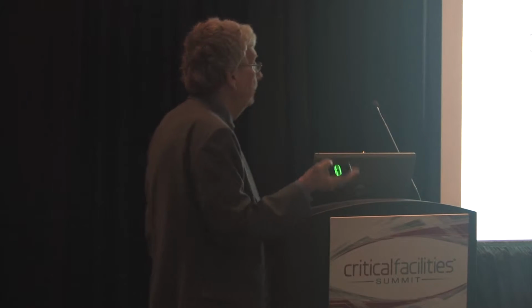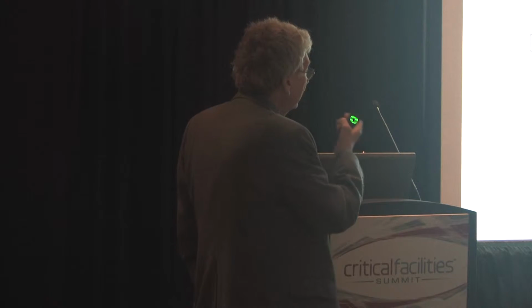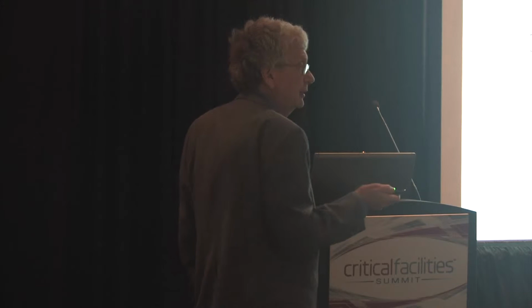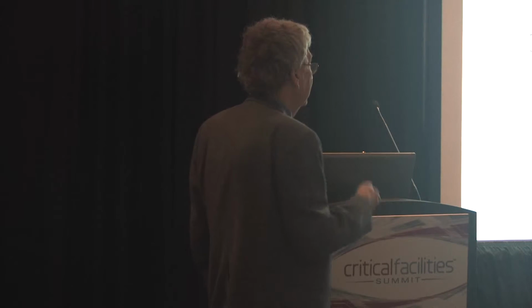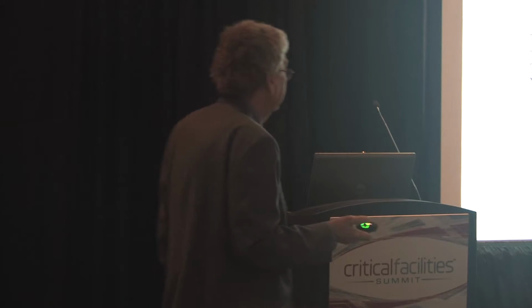So our first point of IT load has been the output of the UPS. Assuming we can segregate out things off the output of the UPS, like CRAC fans, or anything else that's not a pure IT load, that's been a default sort of answer as to what's my IT load. And to a certain extent, that's a good enough answer in many cases. It's certainly a good baseline when you don't compare it to anything, so it's a bit of useful information.